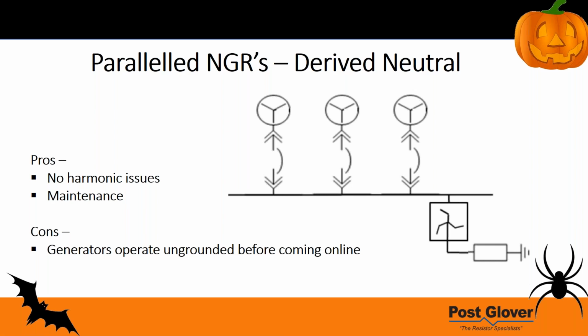So the good news is you don't have a direct connection from the generator to neutral, so you don't have the harmonic issues you'd otherwise have. Also, because they're independent of each other and the ground source, you don't have any maintenance issues. Just like the first one, you're going to be online and good to go. But as you can probably tell, since this box here is the only ground fault path, when you're winding up and you're not quite dialed in yet on the generator, you're going to be ungrounded, right? So that's the big negative for this one.